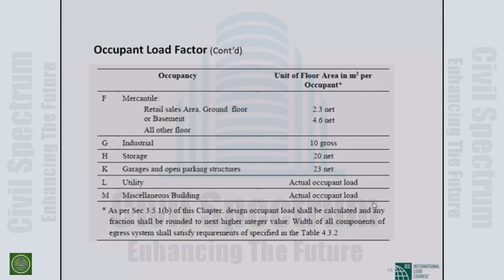If this density is 10 square meters per person, a garments factory cannot run, because a person working at a sewing machine has to hand over the product to the next person by moving. But if it is a 10 meter gap, productivity cannot be achieved. Actually, that is not correct as per NFPA also. So for garments you need some special consideration. That's why as per BNBC, you need a performance-based design. Though it is G for 10, it is not acceptable, particularly in the sewing area. Other than the sewing area, it is fine.